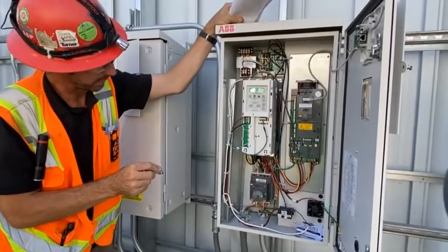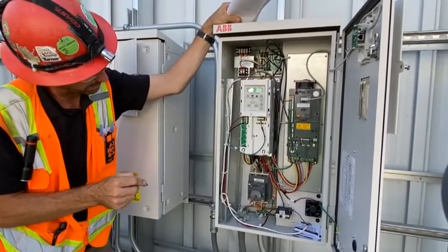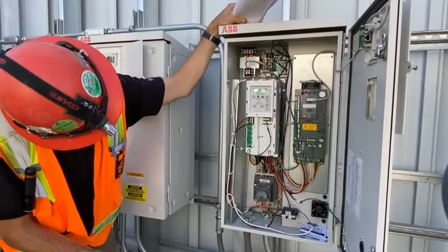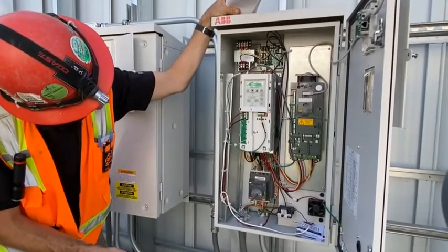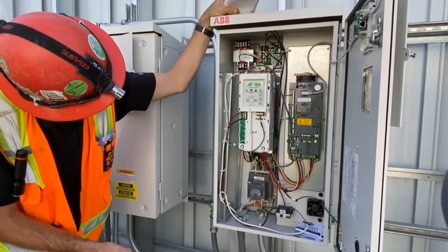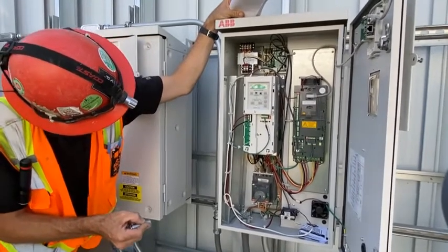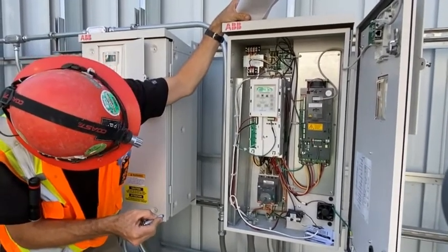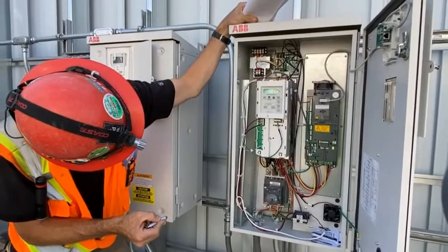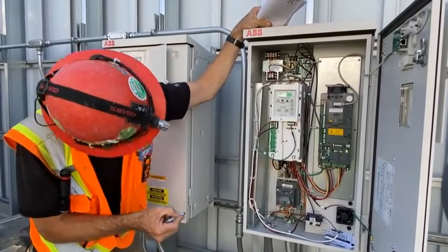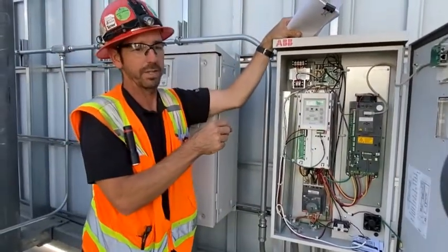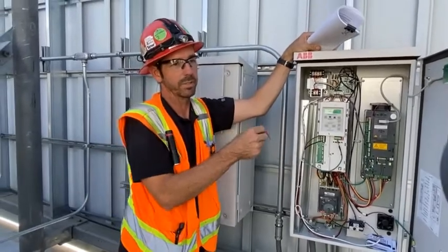This is the main disconnect down here. So right now I've turned it off. There's still power underneath here. We're not breaking the plane of the compartment. After the disconnect switch, we have a couple of input fuses right here. And after that, the power switches off into the bypass or the drive mode.